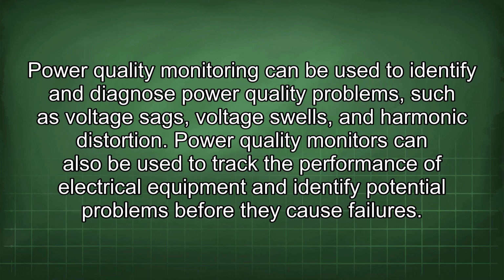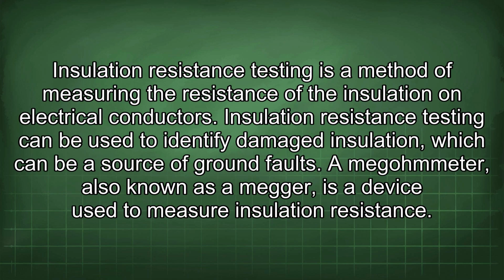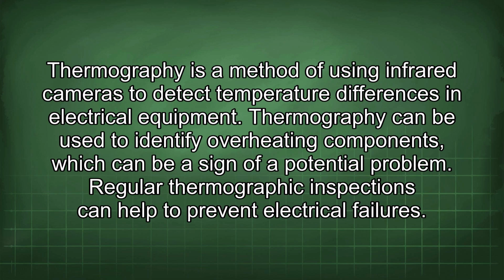Power quality monitors can also be used to track the performance of electrical equipment and identify potential problems before they cause failures. Insulation resistance testing is a method of measuring the resistance of the insulation on electrical conductors. Insulation resistance testing can be used to identify damaged insulation, which can be a source of ground faults. A megohmmeter, also known as a megger, is a device used to measure insulation resistance.